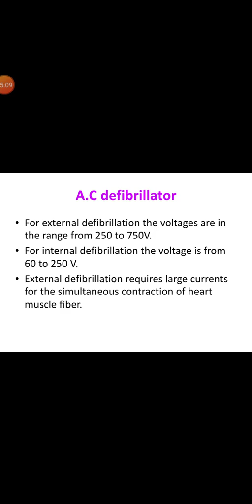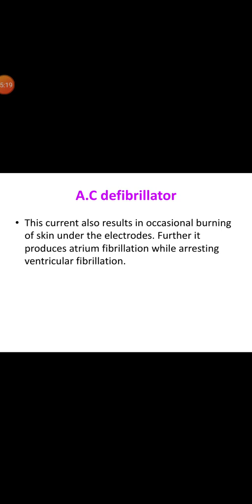For external defibrillation, the voltages are in the range from 250 to 750 volts. For internal defibrillation, the voltage is from 60 to 250 volts. External defibrillation requires large current for the simultaneous contraction of the heart muscle fibers. This current also results in occasional burning of the skin under the electrodes. Further, it produces atrial fibrillation while arresting ventricular fibrillation.